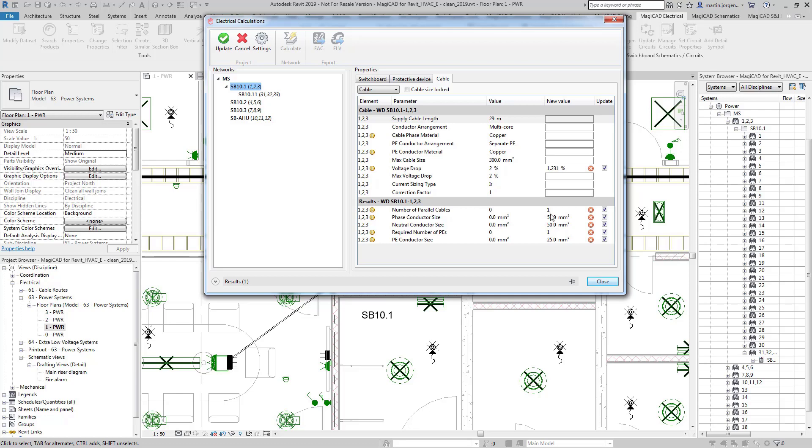And then we can see here it's selected a 50 mil squared cable to provide the power to this circuit and then a 25 mil squared separate copper conductor for the earth.